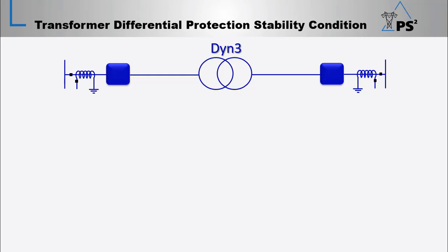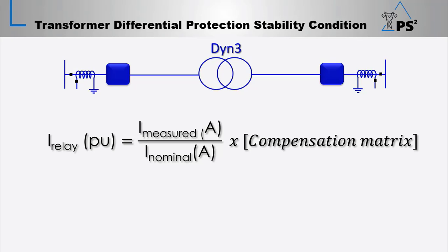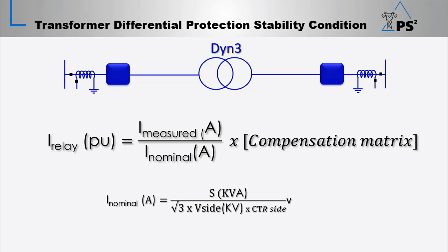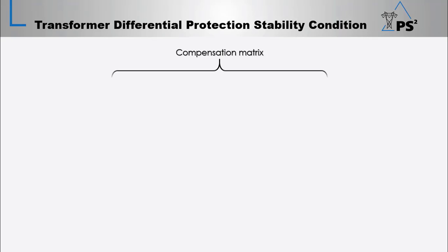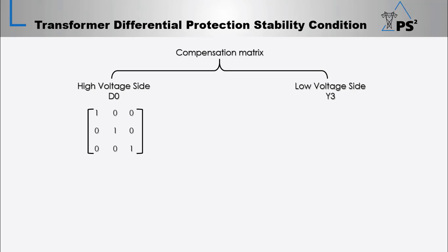Now for the transformer differential protection calculations, the relay uses the per unit current values, where I relay equals I measured in amps over I nominal in amps, multiplied by the compensation matrix. I nominal is the quotient of the apparent power over root 3 multiplied by the transformer side voltage and CT ratio. The compensation matrix is used for both transformer sides, where for the delta side, which is the reference winding, matrix 0 is used. Matrix 0 means multiplying the current values by 1, no changes in the magnitudes or angles. And for the star side, matrix 3 must be used according to the transformer vector group DYN3.